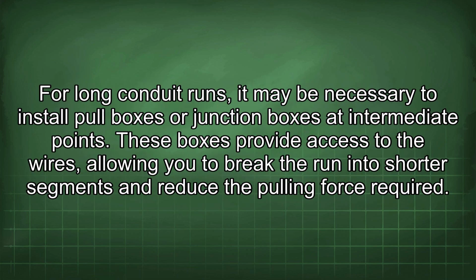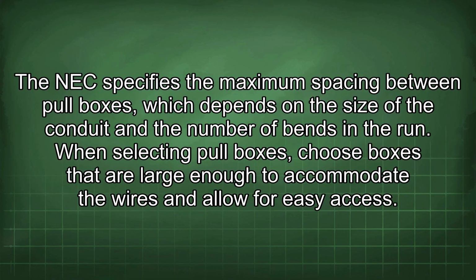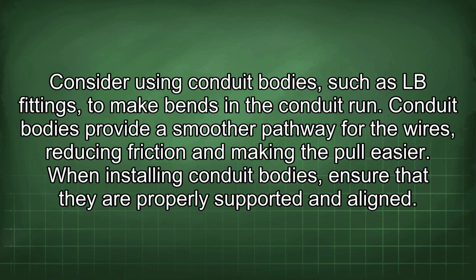For long conduit runs, it may be necessary to install pull boxes or junction boxes at intermediate points. These boxes provide access to the wires, allowing you to break the run into shorter segments and reduce the pulling force required. The NEC specifies the maximum spacing between pull boxes, which depends on the size of the conduit and the number of bends in the run. When selecting pull boxes, choose boxes that are large enough to accommodate the wires and allow for easy access. Consider using conduit bodies, such as LB fittings, to make bends in the conduit run. Conduit bodies provide a smoother pathway for the wires, reducing friction and making the pull easier.